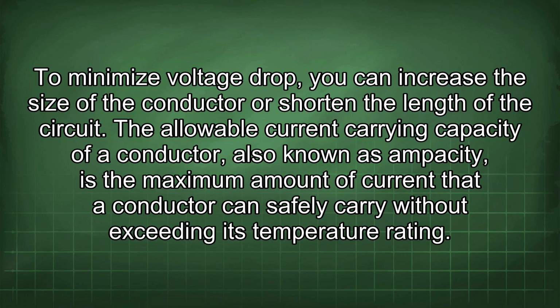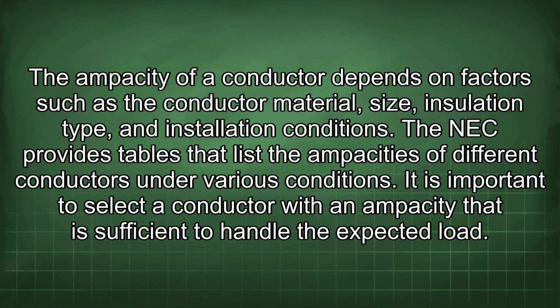The allowable current carrying capacity of a conductor, also known as ampacity, is the maximum amount of current that a conductor can safely carry without exceeding its temperature rating. The ampacity of a conductor depends on factors such as the conductor material, size, insulation type, and installation conditions. The NEC provides tables that list the ampacities of different conductors under various conditions. It is important to select a conductor with an ampacity that is sufficient to handle the expected load.